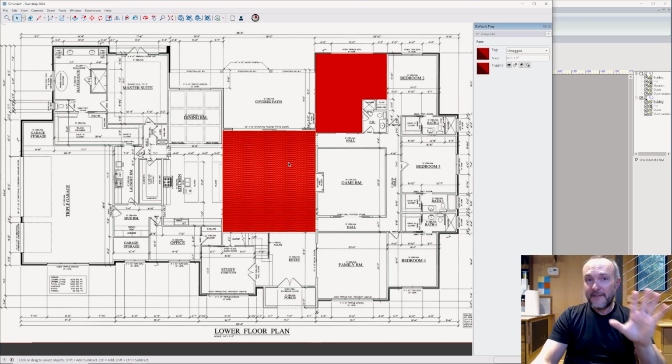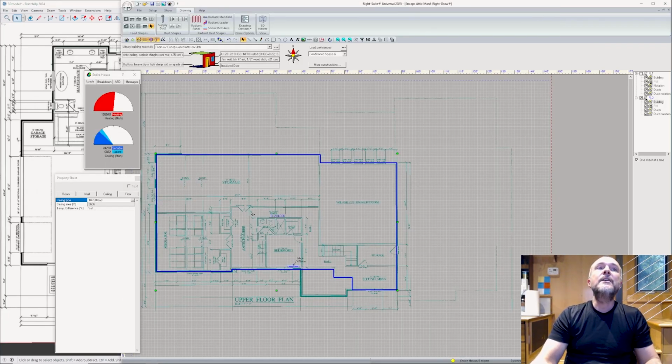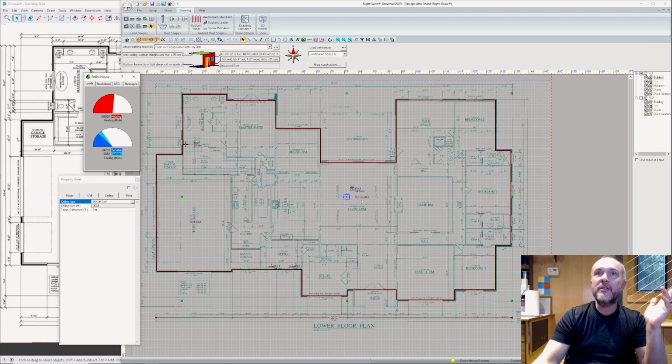Okay, so the surface area is what we're worried about here, and that's why I'm making a big deal about it. So now let's take this 10,548 BTUs, and in the summertime, 31,000 BTUs of cooling. Okay, so now we're going to switch over to how I do the full conditioned attic. And you can see that on floor 1, by the way, just before we flip over to the other model, we've got 1,076 CFM being delivered to floor 1.